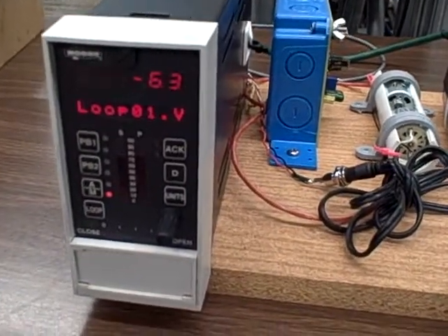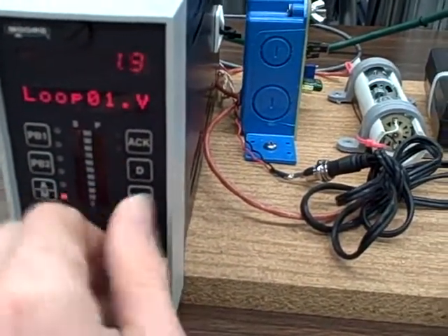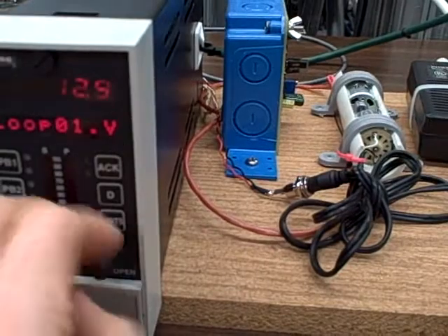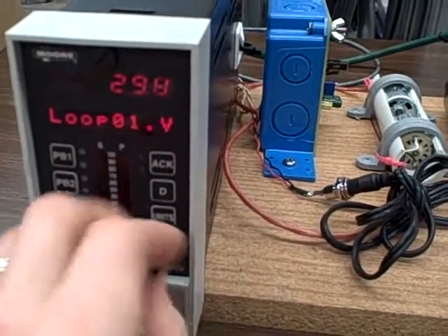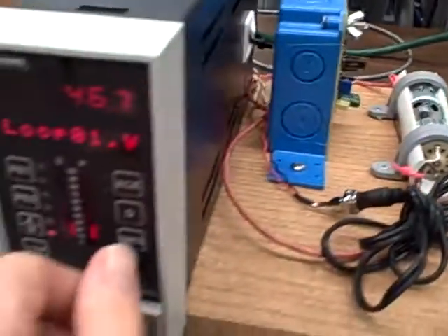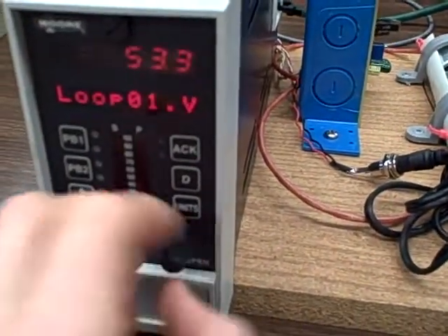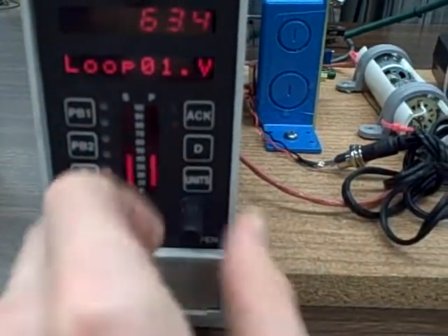To do this, first I'm going to start in manual mode, and I'm going to increase the output until we get the motor to spin manually. This is not automatic, so I'm simply adjusting power to the motor by hand until we get some motion out of it. You can actually see it spinning right there. You'll see the tape that we're using for a coupling between the motor and the generator. I'm going to increase this until I get somewhere around 50% on my process variable scale.